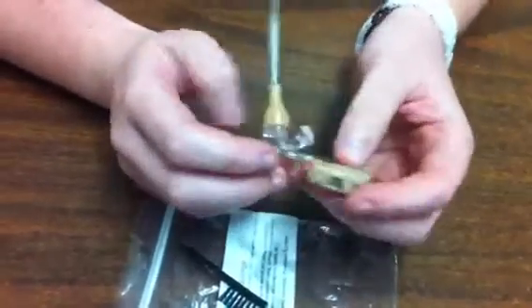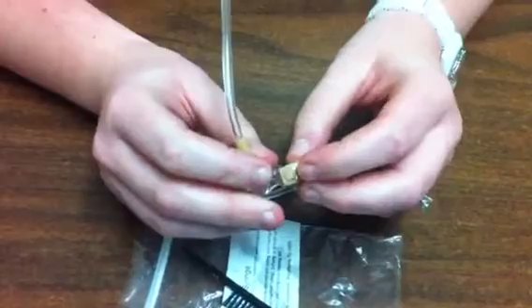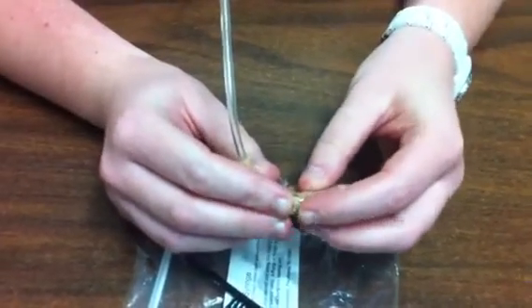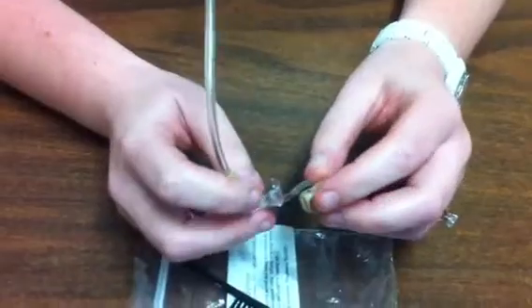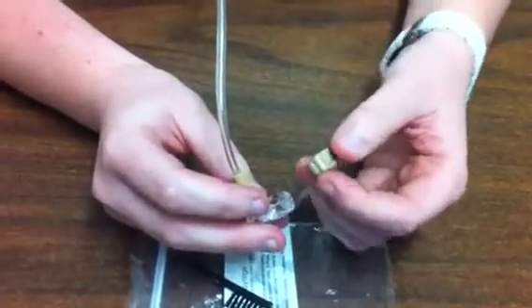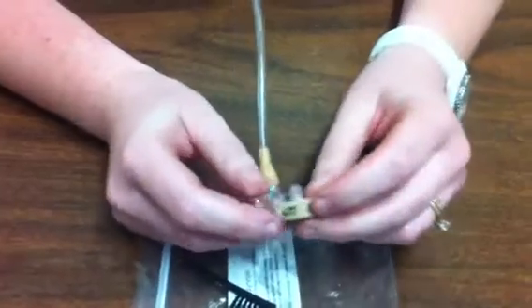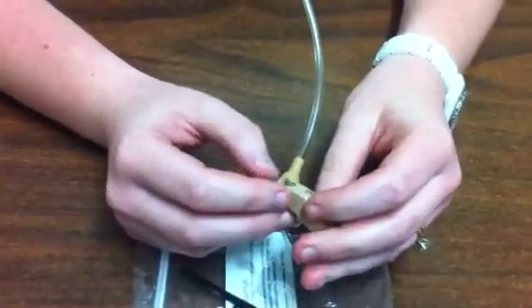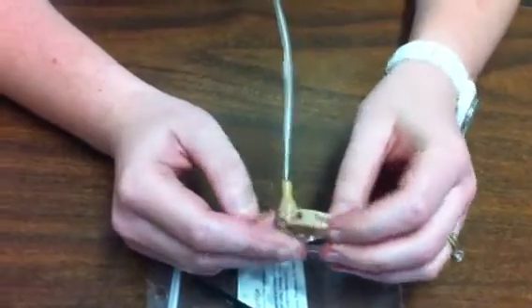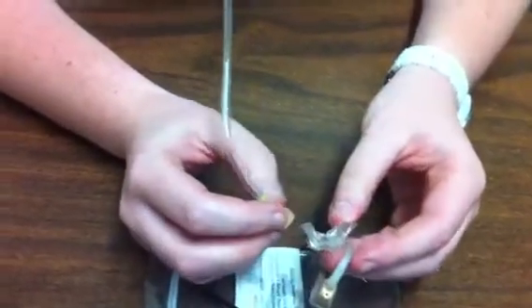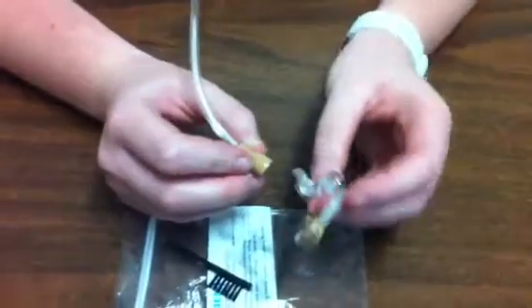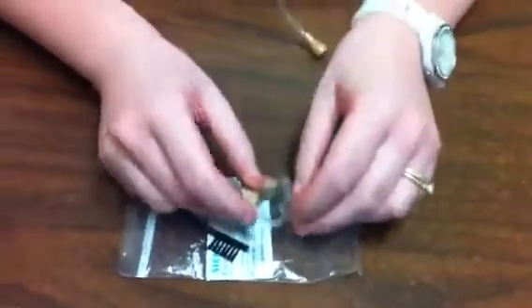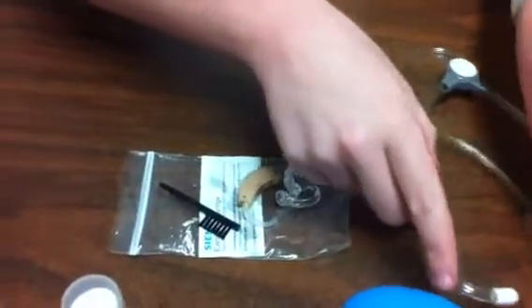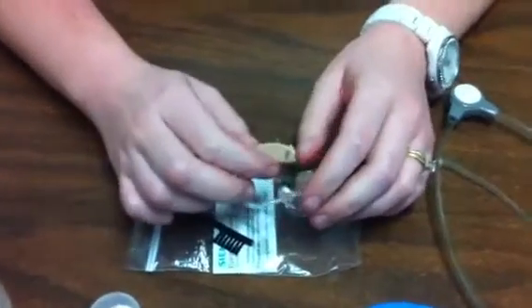So just to check to make sure there's no strange noises or static in the hearing aid. And while you're listening, doing those sounds, you're going to want to be manipulating it with your hands, putting the volume up and down, changing it from microphone to telephone. And if it sounds okay and there's no static in the connection, then you're fine. Now when you do this, you can use gloves or just use extra caution when checking.